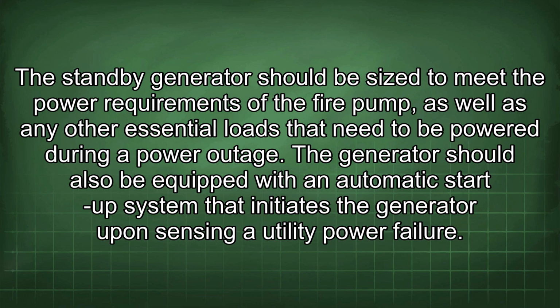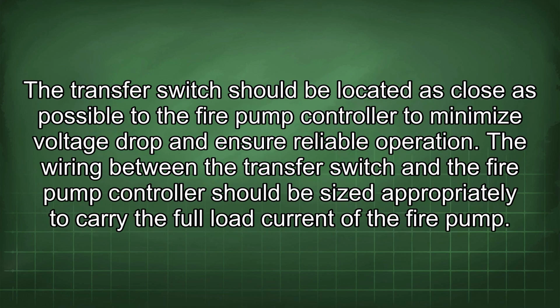The generator should also be equipped with an automatic startup system that initiates the generator upon sensing a utility power failure. The transfer switch should be located as close as possible to the fire pump controller to minimize voltage drop and ensure reliable operation. The wiring between the transfer switch and the fire pump controller should be sized appropriately to carry the full load current of the fire pump.